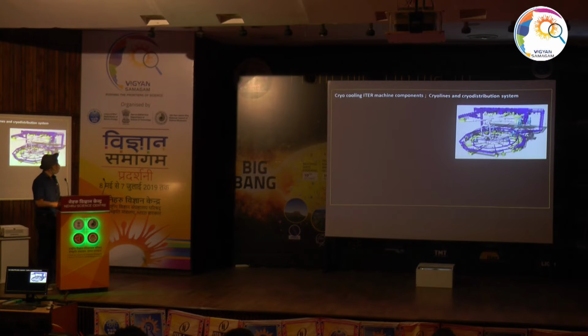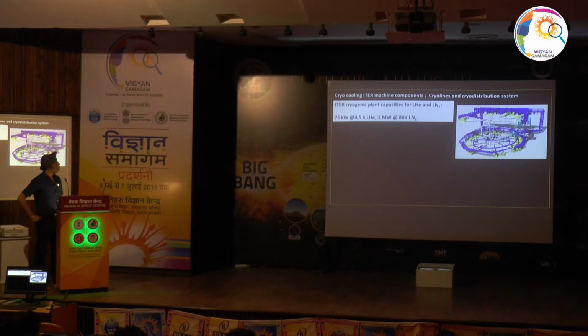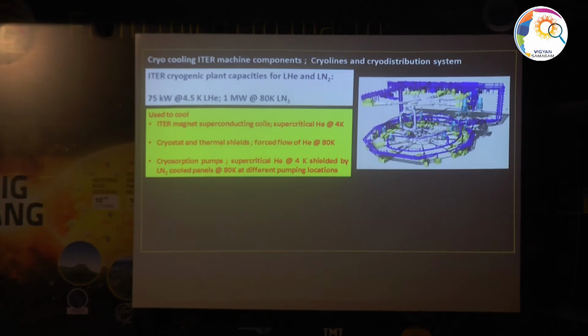The third system is the cryo cooling system, or the cryo distribution system. This one is also as complex as the cooling water system, and its main function is to support the cryolines, and the cryo distribution system supports the liquid helium and liquid nitrogen plant facilities at ITER. The liquid helium plant facility is 75 kilowatts at 4.5 Kelvin, and the liquid nitrogen facility is 1 megawatt at 80 Kelvin. As it was said during the inauguration session, this is one of the largest cryo systems on a single platform available worldwide. Though LHC also has a number of cryo plant systems, in terms of the size of a single sub plant, this is one of the largest.